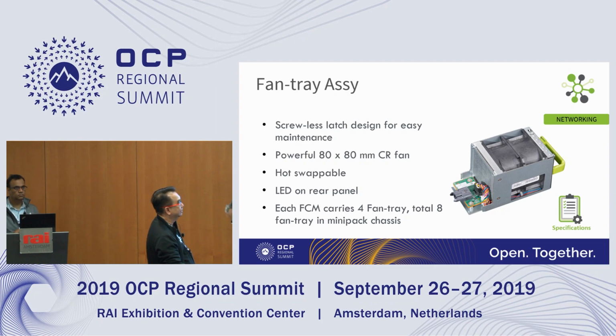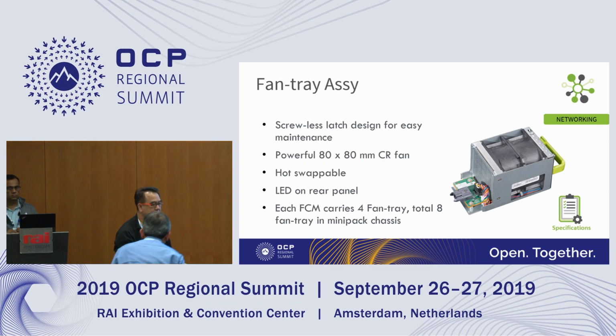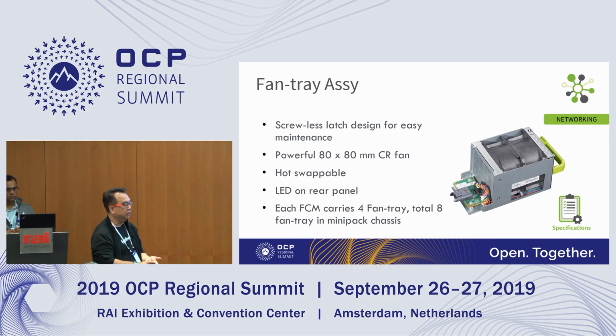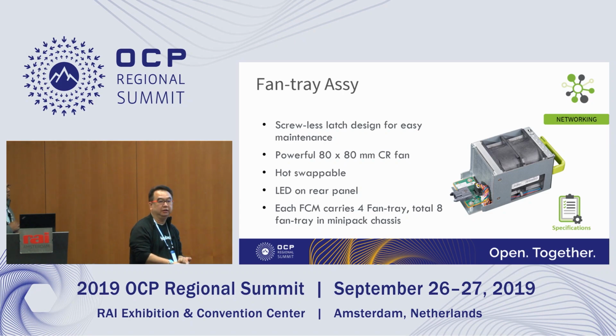For the fan tray assembly, it's a toolless design—we don't use screws to latch the fan tray, which saves a lot of time in the data center if they need to replace a fan. We're utilizing 80 by 80 millimeter counter-rotating fans, which provide high pressure and sufficient airflow. It's hot swappable, and we have an LED indicator on the back to indicate a failure on the fan tray assembly.